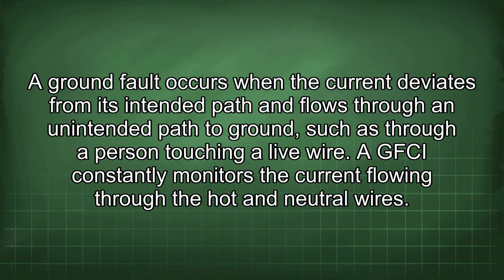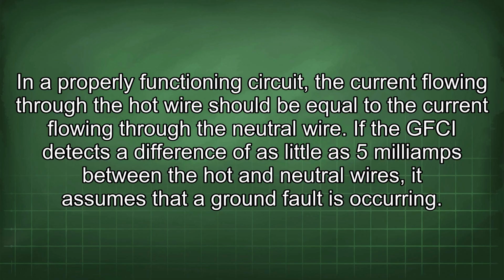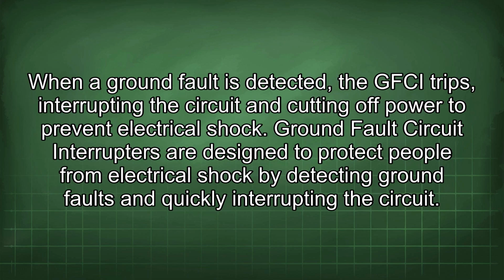A GFCI constantly monitors the current flowing through the hot and neutral wires. In a properly functioning circuit, the current flowing through the hot wire should be equal to the current flowing through the neutral wire. If the GFCI detects a difference of as little as 5 mA between the hot and neutral wires, it assumes that a ground fault is occurring. When a ground fault is detected, the GFCI trips, interrupting the circuit and cutting off power to prevent electrical shock.